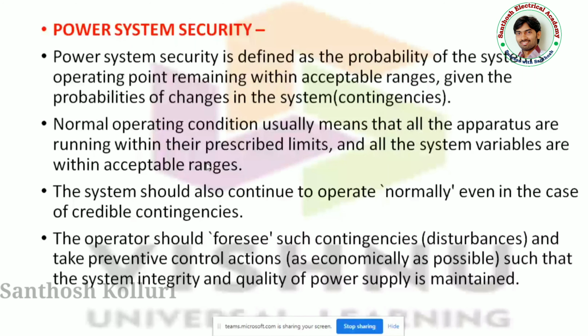What do you mean by credible contingencies? If any disturbance happens, let us take a sudden surge in the voltage, if it is operating around 240 volts instead of 230 volts, so it is a sudden surge and it will last for limited cycles that can be withstood by the system or by the equipment, then that contingency is called a credible contingency.